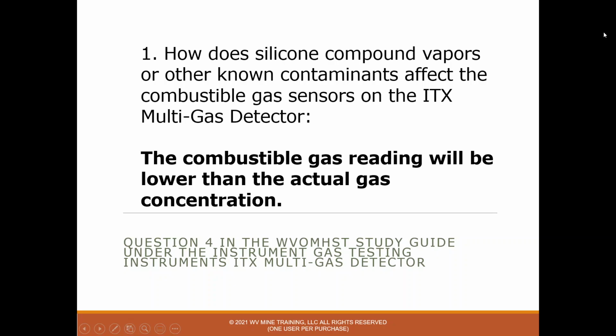So the best thing, I just tell my students, if you see silicone compound vapors or other known contaminants, look for the word lower in the answer: the combustible gas reading will be lower than the actual gas concentration, which is not good. You could have 5% methane and your instrument's telling you you have 2%, which still requires you to turn the power off and all that, but still, the reading that it's going to display will be lower than what's actually there.